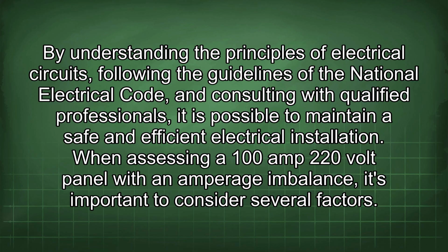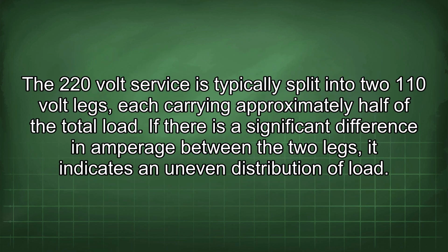When assessing a 100 amp 220 volt panel with an amperage imbalance, it's important to consider several factors. The 220 volt service is typically split into two 110 volt legs, each carrying approximately half of the total load. If there is a significant difference in amperage between the two legs, it indicates an uneven distribution of load.